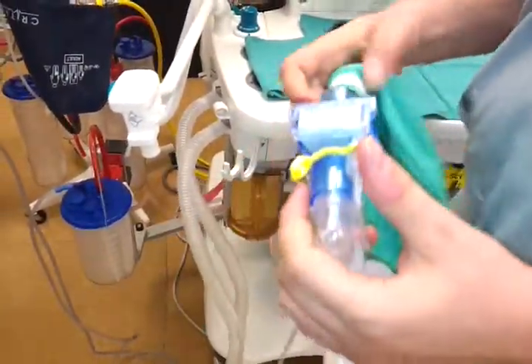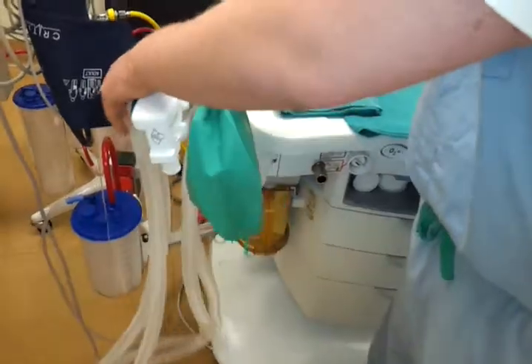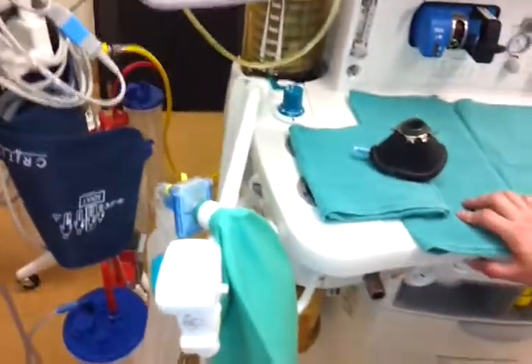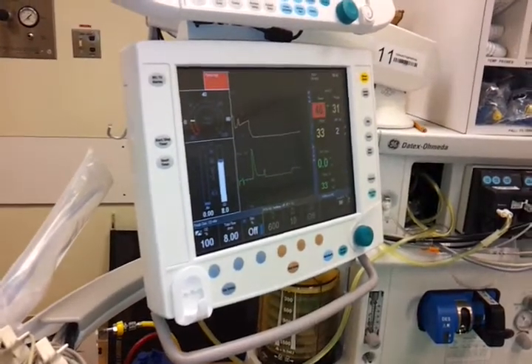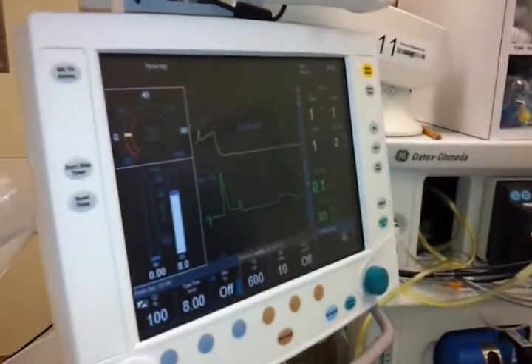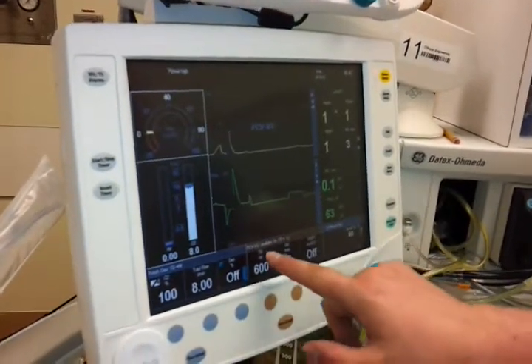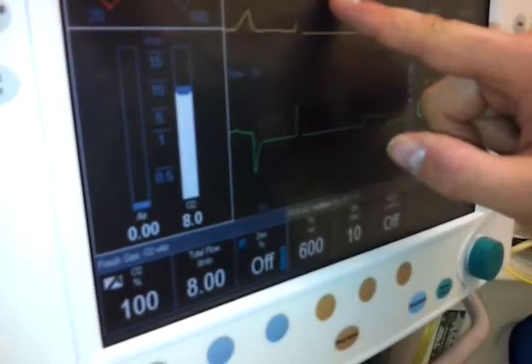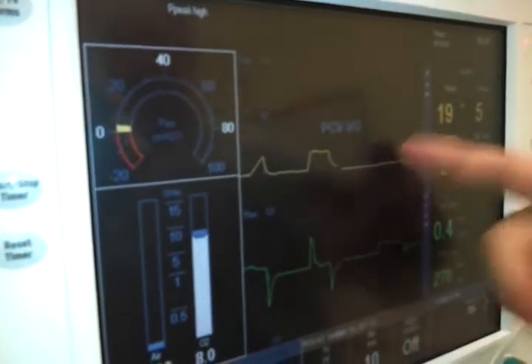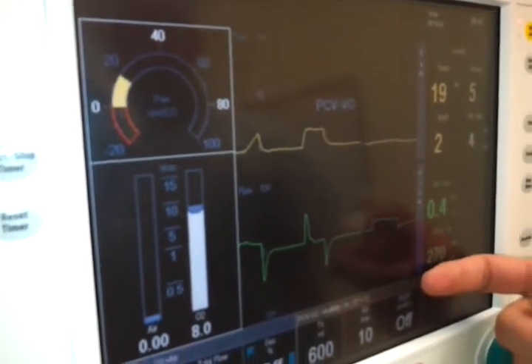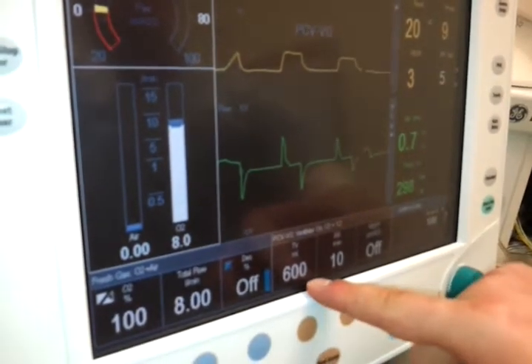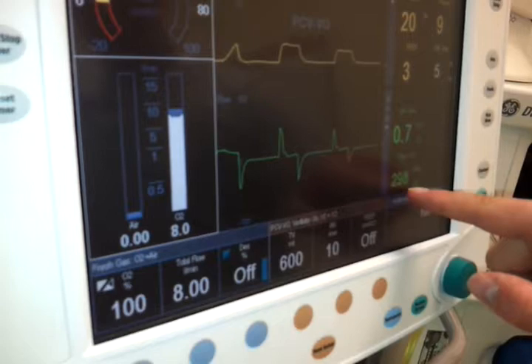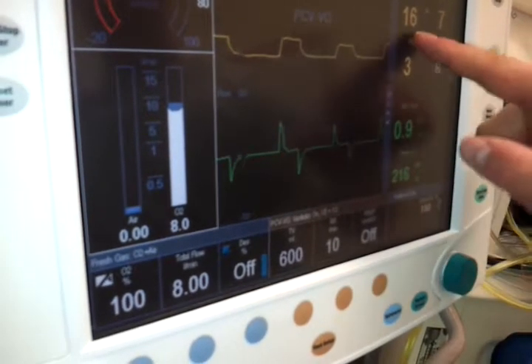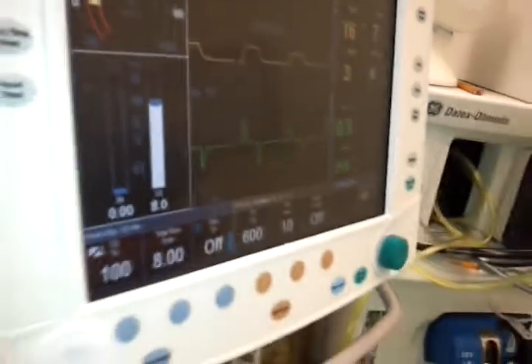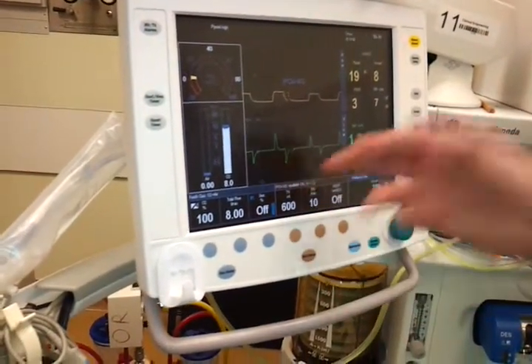Yeah, and I made a mistake. So you have to take the patient, well, unocclude it and hook it up to a test lung. So, yeah, that's fine. So we're going to switch it over to vent. The mode it always starts out in is pressure control ventilation with volume guaranteed. So it's kind of like PRVC. You have a set tidal volume, and it's only giving about 300 mils right now, 216. So it's going to increase the pressure until it hits that. You want it to be within 7% of the 600, whatever you have set.